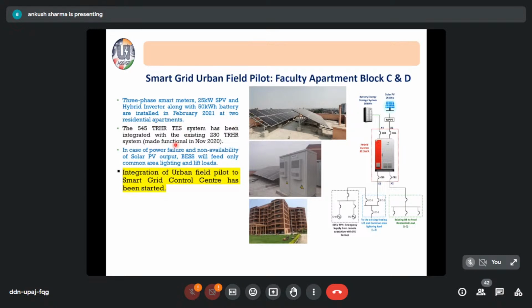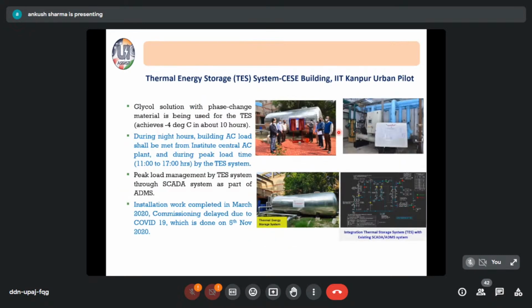In urban, we also have a thermal energy storage system, with a capability of 775 ton hour. This tank contains phase change material, which is cooled down to -8 degrees centigrade, and the cooling is retained within this thermally insulated tank.